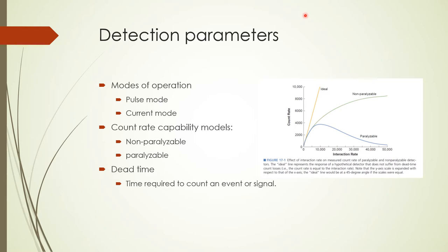For paralyzable systems operated in high radioactivity environments, signals or pulses are ignored during the dead time and any subsequent signal extends the dead time, so the detector eventually stops counting. The measured count rate increases to a peak and then declines, as the curve shows.